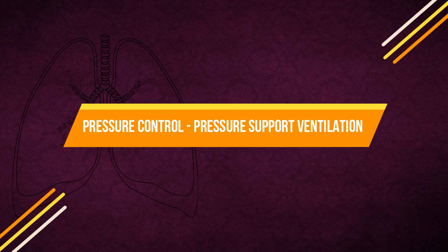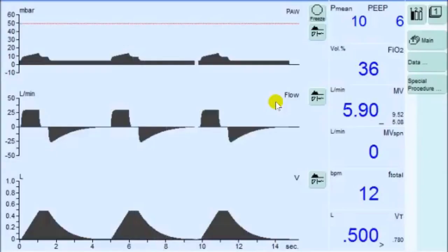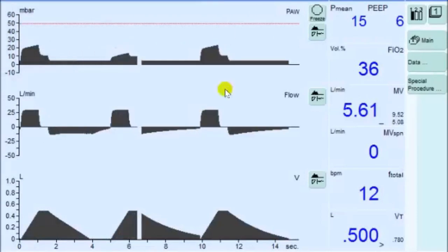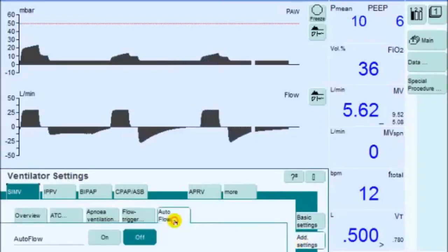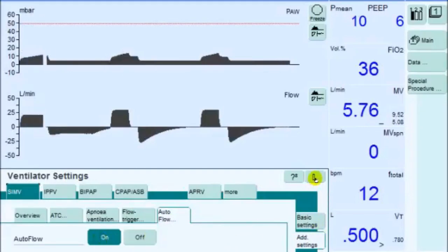The next mode is Pressure Control Pressure Support Ventilation. The patient can breathe spontaneously at PEEP level, and every detected inspiration effort can be pressure supported. The absolute level of pressure support is defined by inspiratory pressure. The duration of inspiration is flow-cycled and depends on the lung mechanics of the patient. The patient determines the number, point of time, and duration of the pressure-supported breaths. If the breathing frequency is lower than the set backup respiratory rate or there is no spontaneous breathing, machine-triggered flow-cycled mandatory breaths with the set inspiratory pressure are applied.